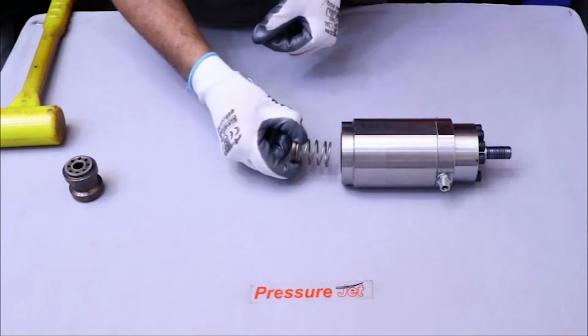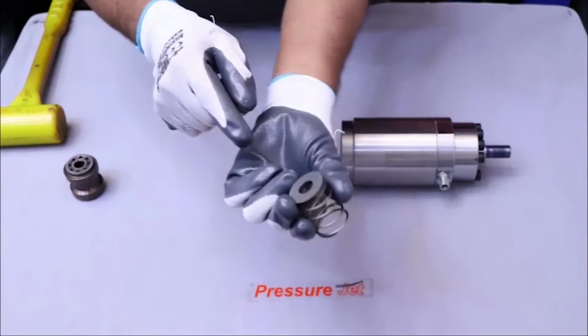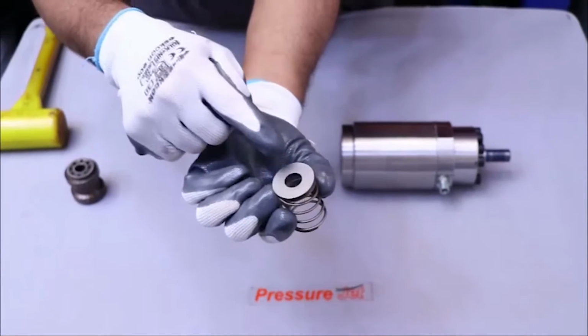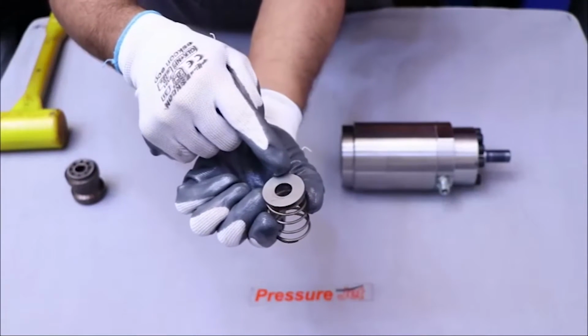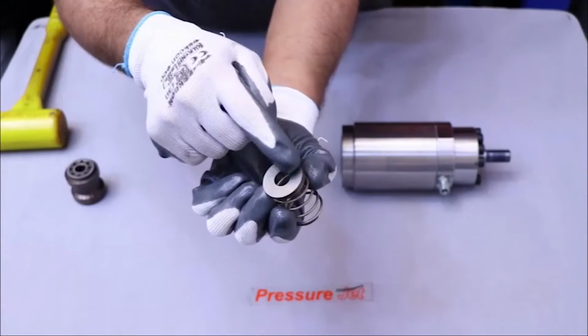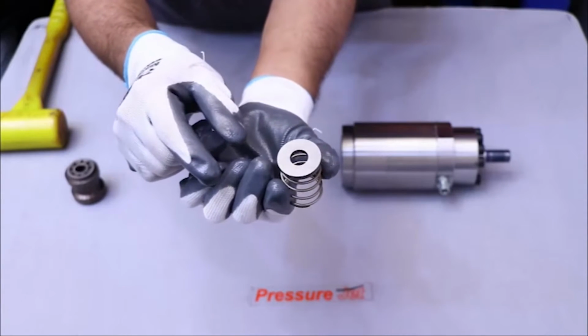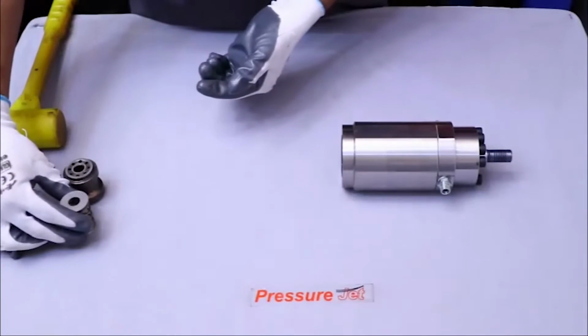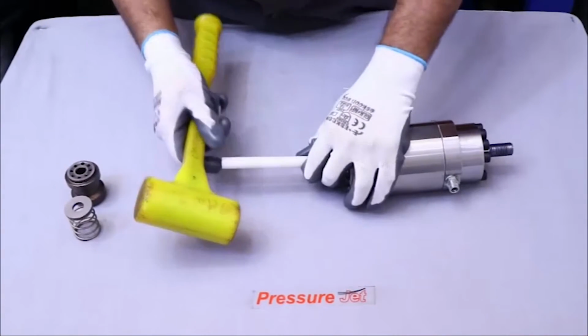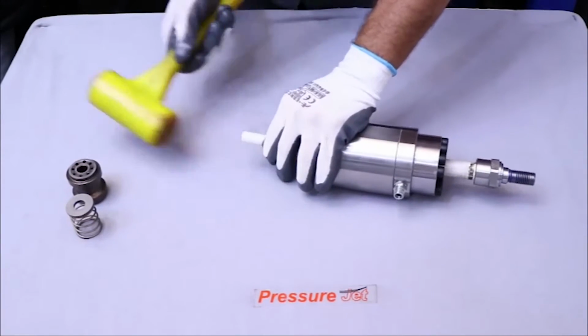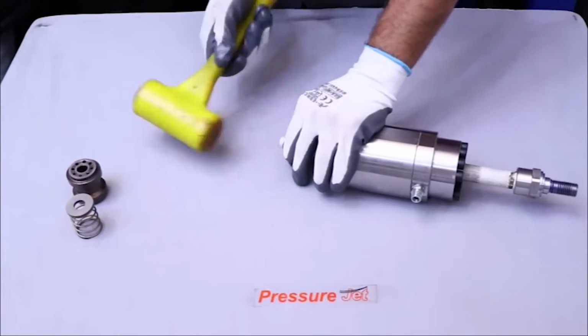After that, remove suction valve and helical spring. Check the surface of suction valve. It should not have scratches. Take a nylon rod and rubber hammer and push it from the opposite side to remove the plunger.